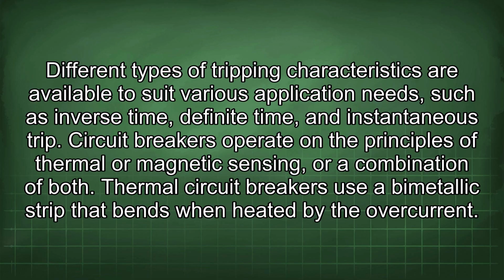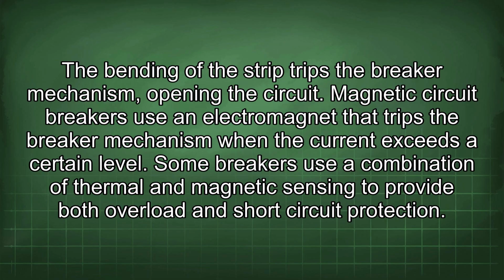Thermal circuit breakers use a bimetallic strip that bends when heated by the overcurrent. The bending of the strip trips the breaker mechanism, opening the circuit. Magnetic circuit breakers use an electromagnet that trips the breaker mechanism when the current exceeds a certain level. Some breakers use a combination of thermal and magnetic sensing to provide both overload and short circuit protection.